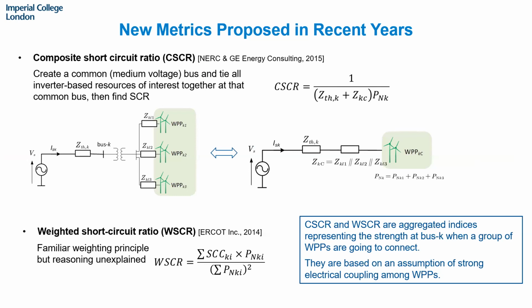These two metrics mainly deal with the case where you're going to connect a group of wind farms to bus K, and you want an overall short circuit ratio to assess the strength at bus K. In that case you need some assumptions, like assuming all the wind power farms in this group are connected to the same MV, and therefore you can do a combination of them, which is actually the way we use in composite short circuit ratio.